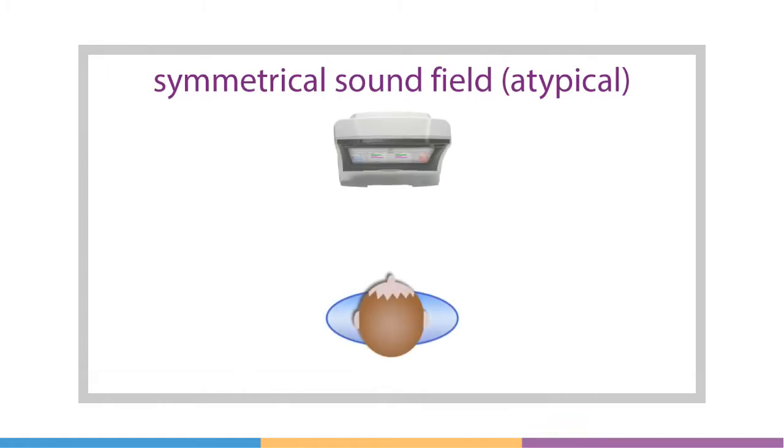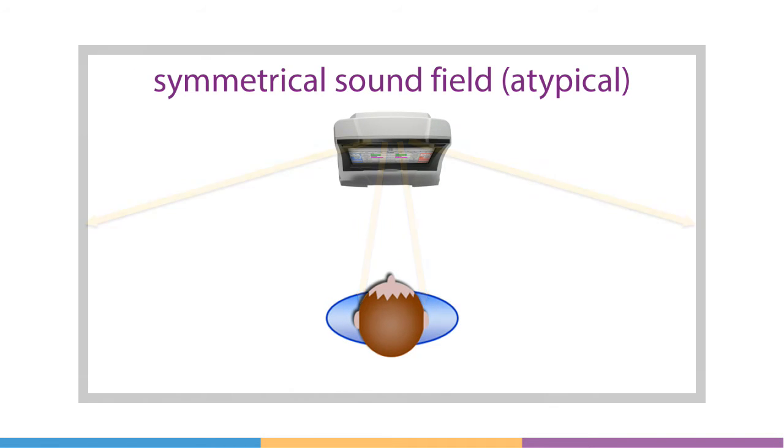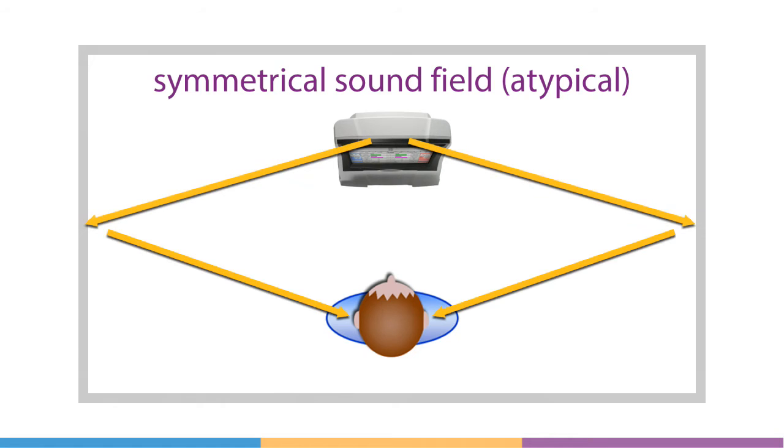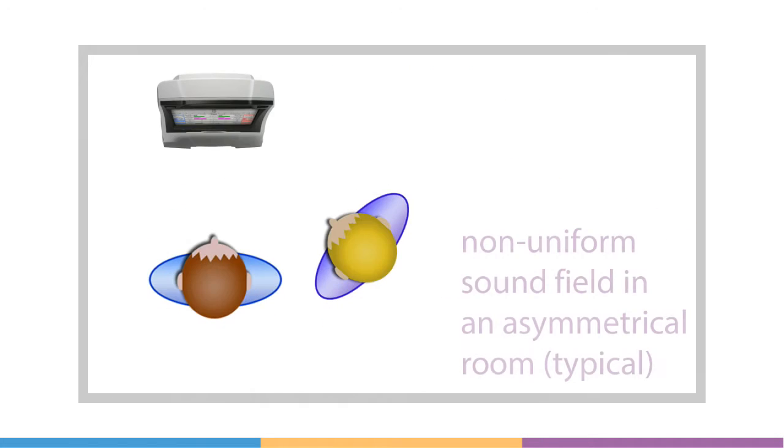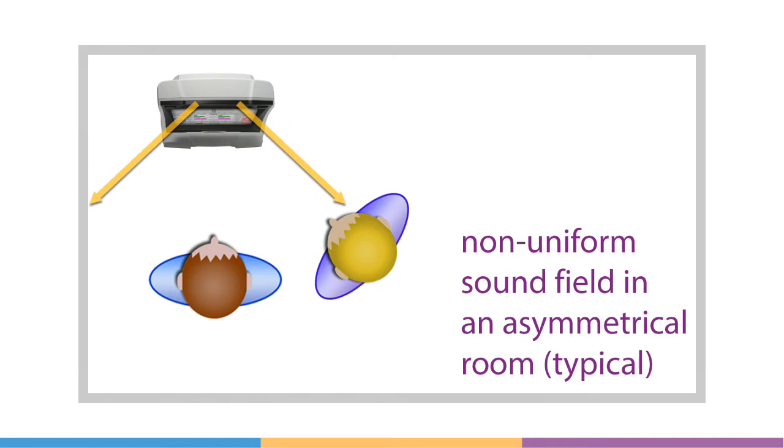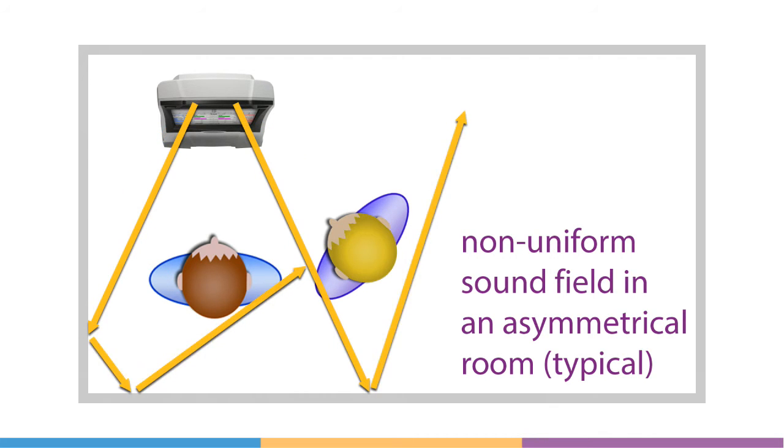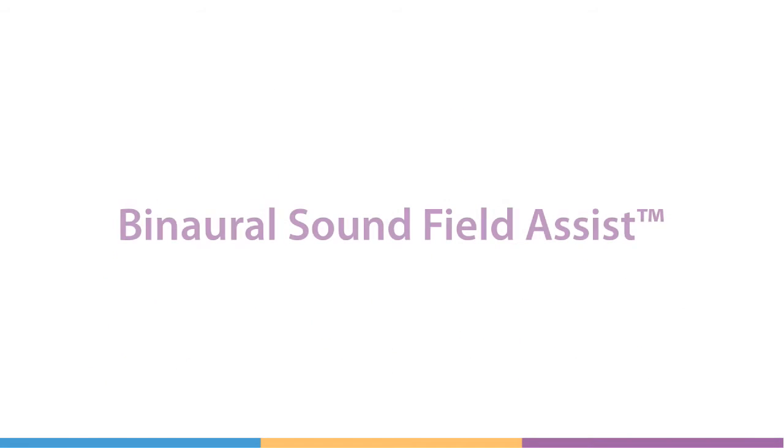Simultaneous binaural on-ear measurements have the added complexity that the acoustic sound field immediately surrounding the subject can vary. Nearby objects, people, or room asymmetry make it difficult to equalize a single sound source at two different locations. This sound field variability, if not properly accounted for, can lead to measurement variability and inaccurate conclusions.